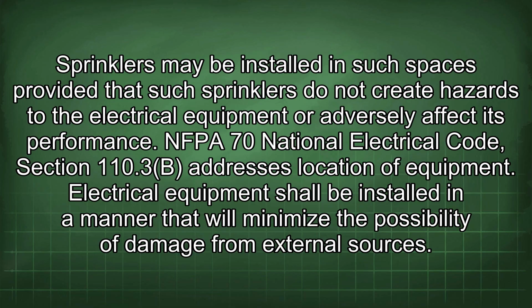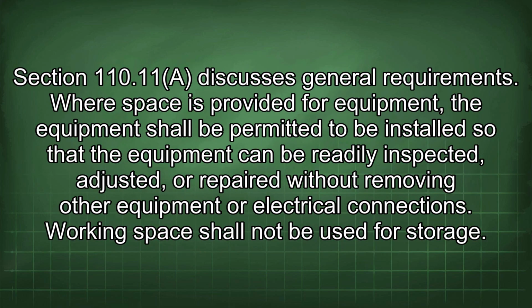NFPA 70 National Electrical Code, Section 110.3b addresses the location of equipment. Electrical equipment shall be installed in a manner that will minimize the possibility of damage from external sources. Section 110.11 discusses general requirements. Where space is provided for equipment, the equipment shall be permitted to be installed so that the equipment can be readily inspected, adjusted, or repaired without removing other equipment or electrical connections. Working space shall not be used for storage.